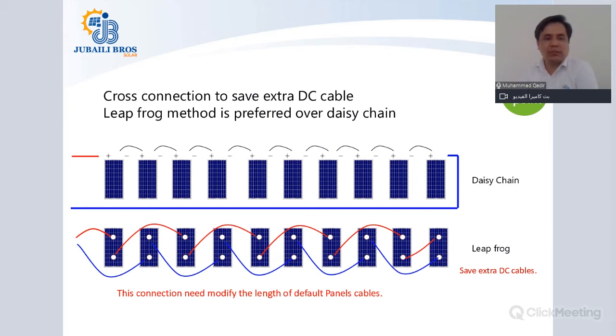Cross connection to save extra DC cables: a leapfrog method is preferred over daisy chain. Most of you would already be aware of this connection type, but it's put here for those who are not aware of the leapfrog type of connection. You can do stringing in two different methods. Connect every solar panel to each other and make a daisy chain, and get the positive and negative ends of your string far from each other.